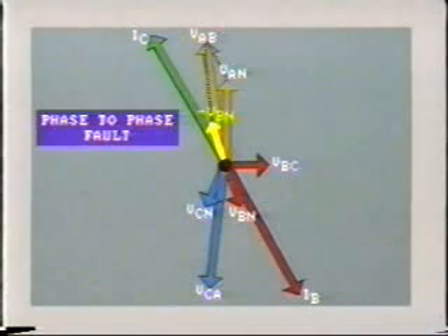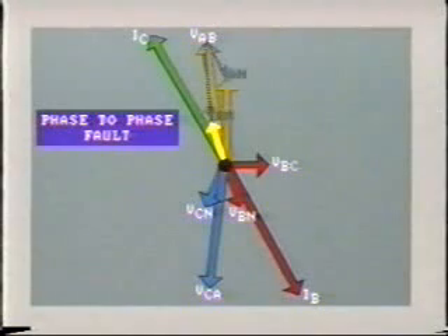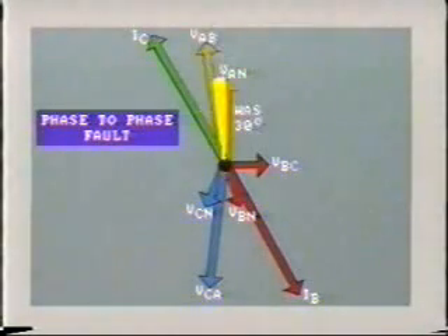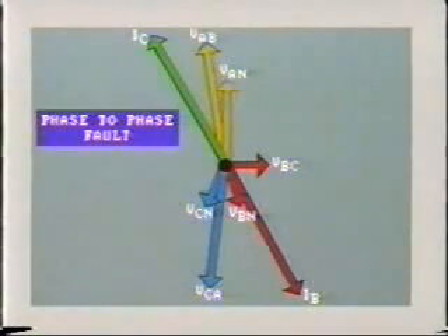As we know, this is the difference between VAN and VBN. Subtracting these phasors, we find that VAB moves back in phase angle. It now leads VAN by less than 30 degrees. The magnitude of VAB is also reduced slightly. We can see that this phase-to-phase fault has seriously distorted our previously balanced condition.